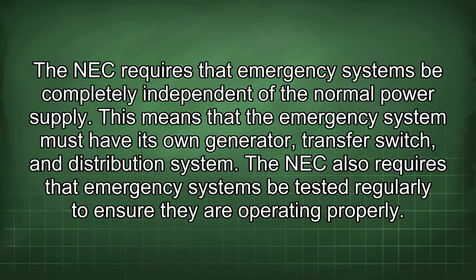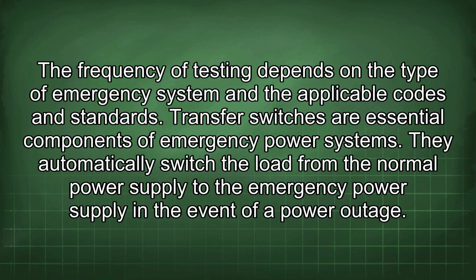The NEC requires that emergency systems be completely independent of the normal power supply. This means that the emergency system must have its own generator, transfer switch, and distribution system. The NEC also requires that emergency systems be tested regularly to ensure they are operating properly. The frequency of testing depends on the type of emergency system and the applicable codes and standards.